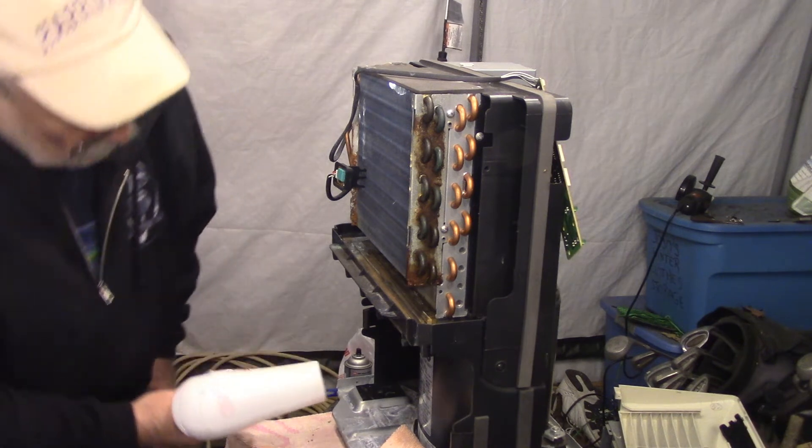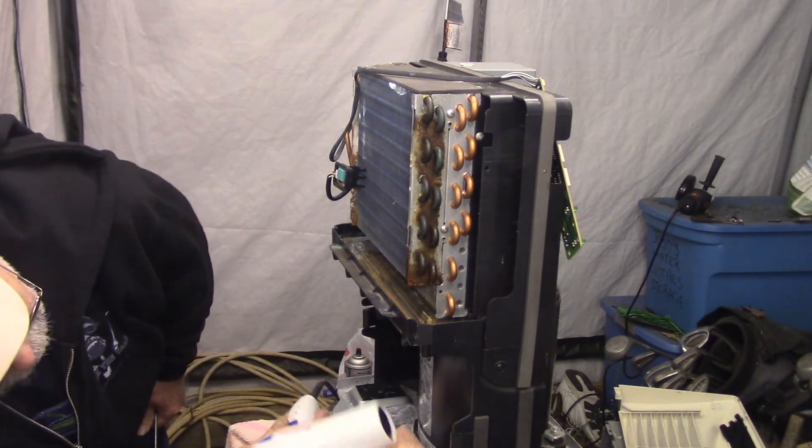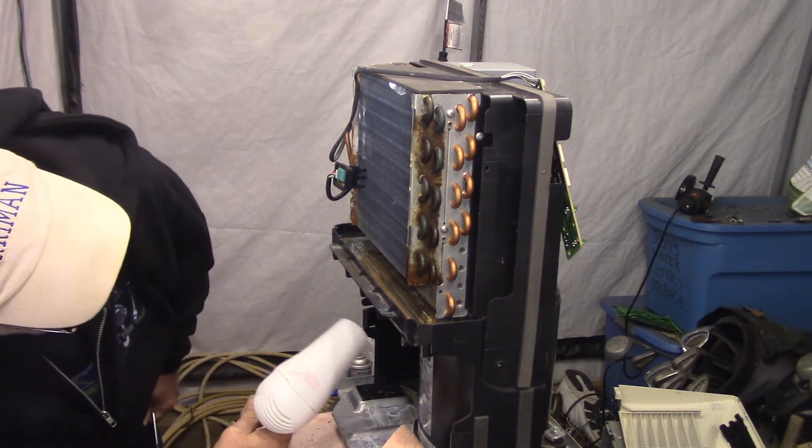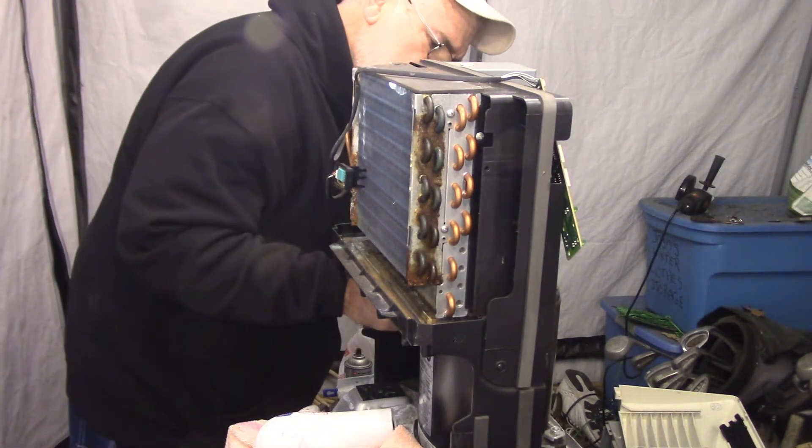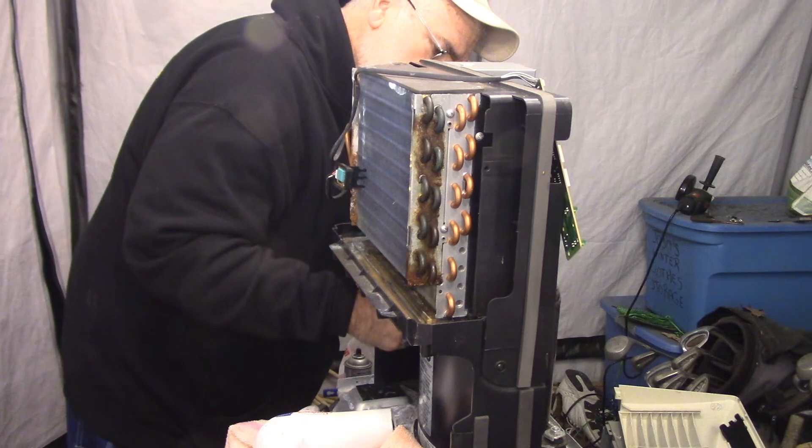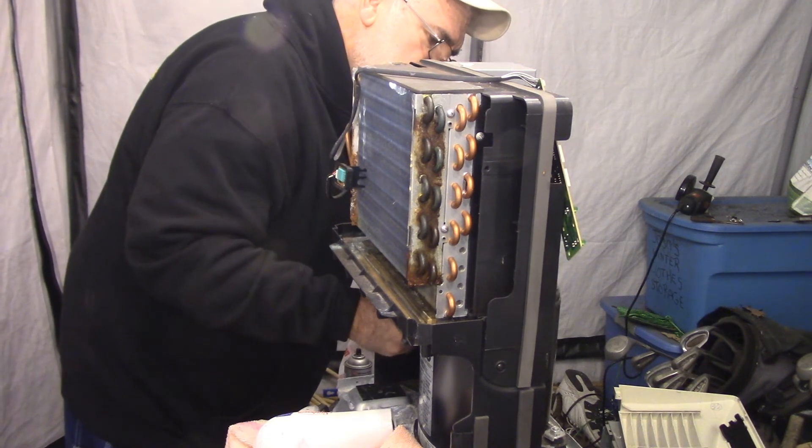I did not see any water in the drip tray there or in the bottom housing. So, hopefully it did not get a lot of water in it while it sat down at the dumpsters. Here I am checking the fill level switch. Mechanically it seems to be functioning properly.